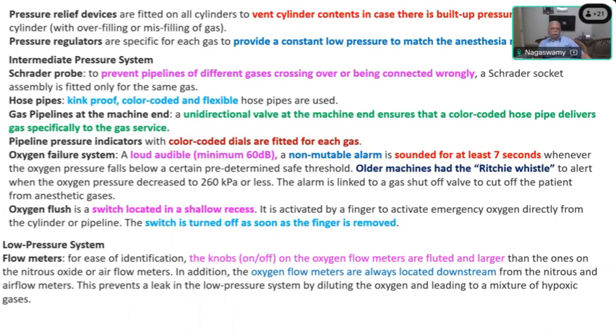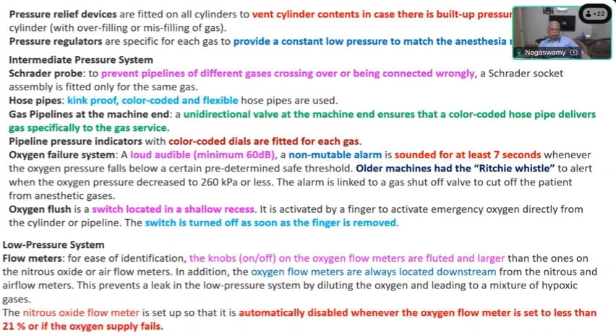And of course, the placement of the flow meter. Earlier, it was oxygen in the first place, followed by nitrous oxide, air, and other gases. Nowadays, oxygen has come to the downstream position, the third position. So you have nitrous oxide, air, and then oxygen, which is supposed to prevent a hypoxic mixture.